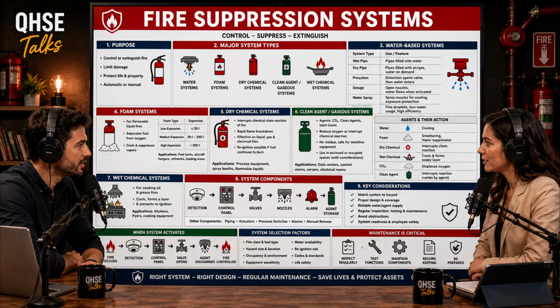Oh, I see where this is going. But if you remove those ceiling panels, the hot gases don't hit a wall. They continue rising straight up through the hole, up into the massive open plenum space between the drop ceiling and the actual structural roof deck. The heat escapes into the attic space. Exactly. Because the heat isn't banking against the drop ceiling where the sprinkler is located, the air temperature around the sprinkler stays cool for much longer.